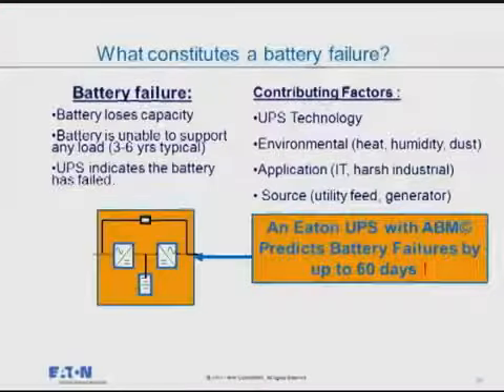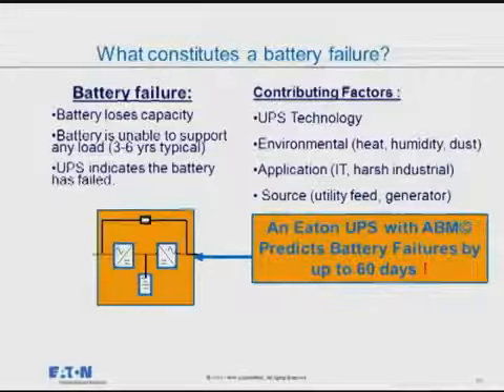So what contributes to battery failure? We talked about usage, but also there's temperature. The hotter the temperature, the more the electrolyte is working, the faster it will decay. So I may not get 5 years in a very hot environment - the electrolyte might be used up in 2 or 3 years. Likewise, cold will extend the life of the battery, but because the electrolyte freezes and turns into a gel, I don't get the power capacity out of the battery. Anyone who's tried to start a car in the winter, right? It's actually better for the battery, you just can't get the juice out of it. So again, temperature affects the lifespan of a battery.